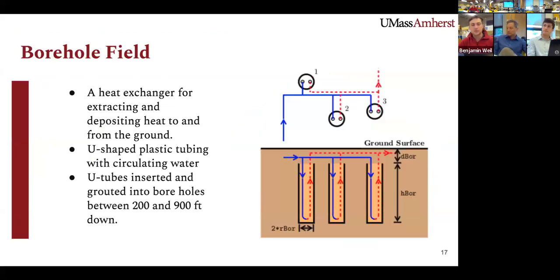But to use a ground source heat pump, you have to install a borehole field. A borehole field is otherwise known as a ground loop. It consists of a series of vertical boreholes drilled into the ground. The borehole field serves as a heat exchanger, allowing heat transfer between the ground and a heat transfer fluid circulating within the pipes. In heating mode, the fluid absorbs heat from the relatively warmer ground and carries it to the heat pump inside the building. In cooling mode, the process is reversed, with heat from the building transferred to the cooler ground.